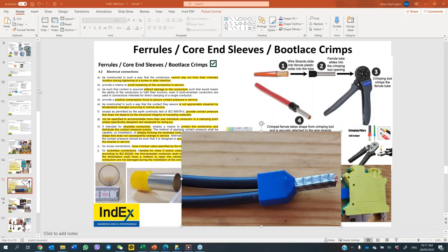Is it necessary to terminate the unused cores in a combination control Ex-de box? So if you're talking about an Ex-de control panel, yes, all unused cores, as per the standard, shall be terminated and earthed back at the non-hazardous area end.